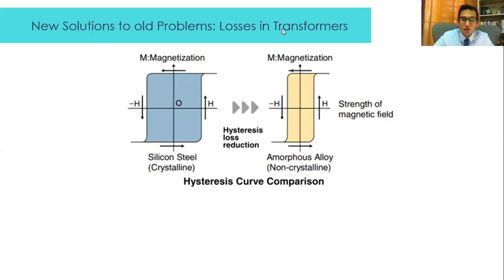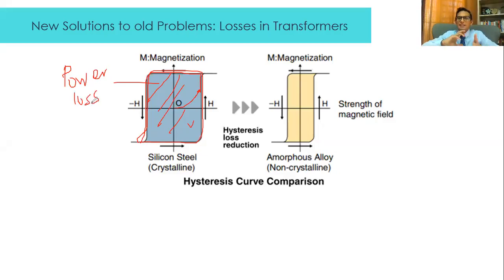This is a hysteresis curve. When energizing the transformer, it goes this way, then this way, and as polarity changes, it goes this way. Whatever is inside represents power loss, due to the reversal of magnetism in the core, since AC is changing. Every time it changes direction, it reverses the magnetism, and every time it reverses magnetism, we find this amount of losses in the system. But we can't do otherwise, it's inherent in the transformer, which is an important component of the power system.